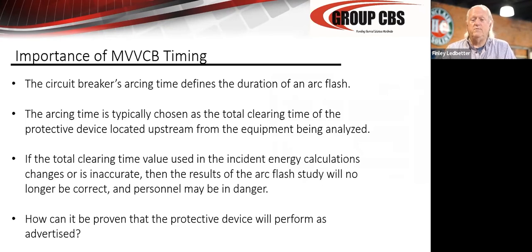We talked about the importance of timing earlier when we got off topic a little bit. Clearing time is very important because it is used in the calculations for your arc flash study. You've had to do these studies, you've had to placard, you've had to train your people, you've had to equip your people. If the breakers do not operate to speed, none of those numbers matter and your people are not protected. OSHA does ask you to prove that the breakers will operate to time and speed, and that can only be done with a timer.